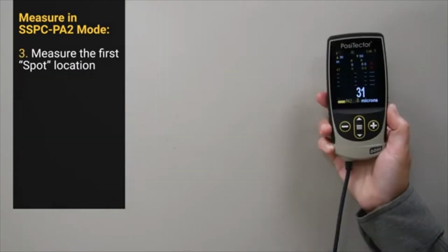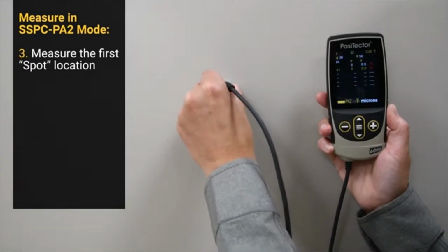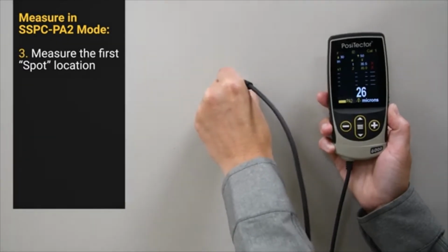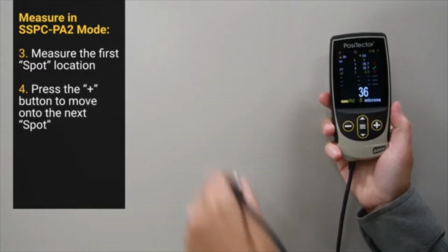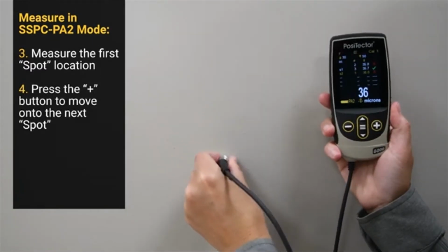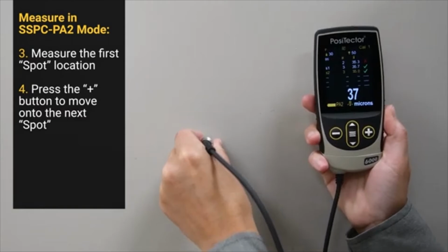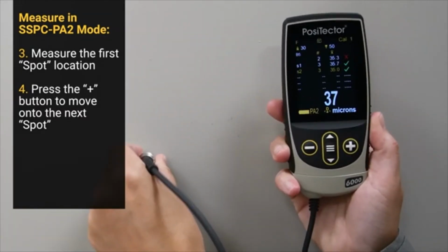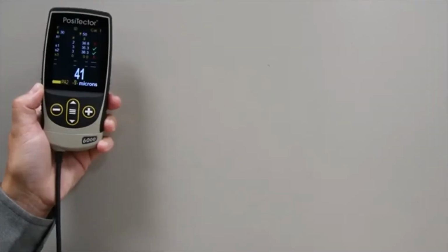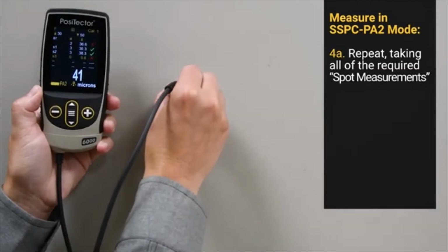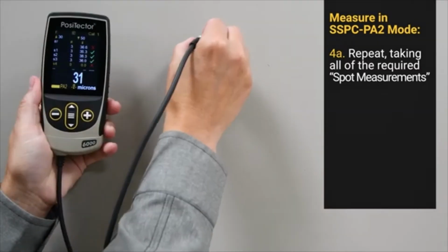Select the first spot location and begin taking measurements. Once the required readings for the first spot are taken, press the plus button to move on to the next spot. A check mark or X will indicate whether the spot measurement passed or failed based on user specifications. Repeat this process until all required spot measurements have been taken.